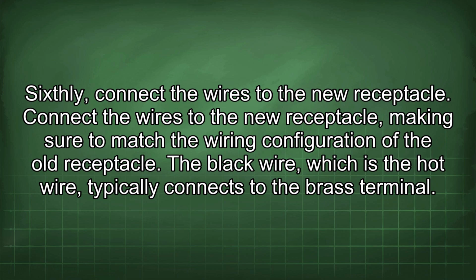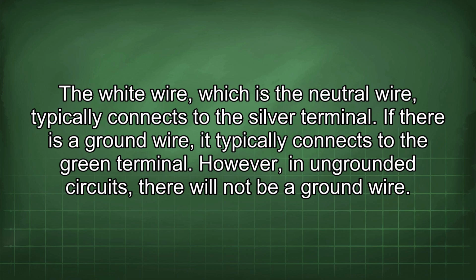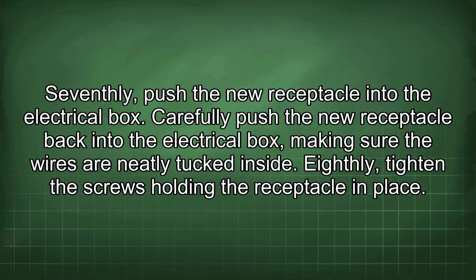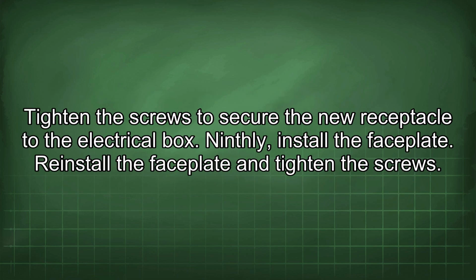The black wire, which is the hot wire, typically connects to the brass terminal. The white wire, which is the neutral wire, typically connects to the silver terminal. If there is a ground wire, it typically connects to the green terminal. However, in ungrounded circuits, there will not be a ground wire. Seventhly, push the new receptacle into the electrical box. Carefully push the new receptacle back into the electrical box, making sure the wires are neatly tucked inside. Eighthly, tighten the screws holding the receptacle in place. Tighten the screws to secure the new receptacle to the electrical box.